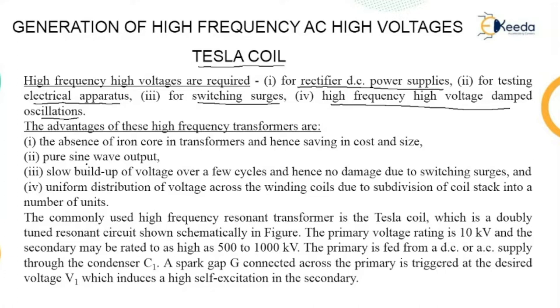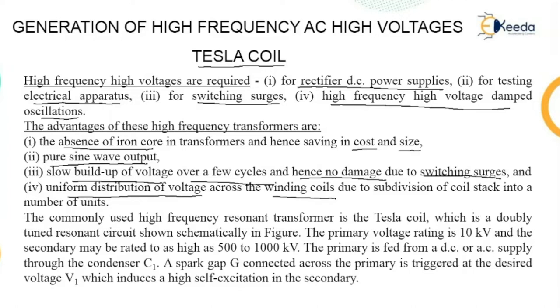There are certain advantages to this. There is absence of an iron core, and hence that saves the cost as well as the size. Since the iron core is absent, the losses are also controlled. Then there is a pure sine wave output. There is a slow buildup of voltage over a few cycles, and hence no damage due to switching surge. The last advantage is uniform distribution of voltage across the winding coils due to subdivision of the coil stack into a number of units.